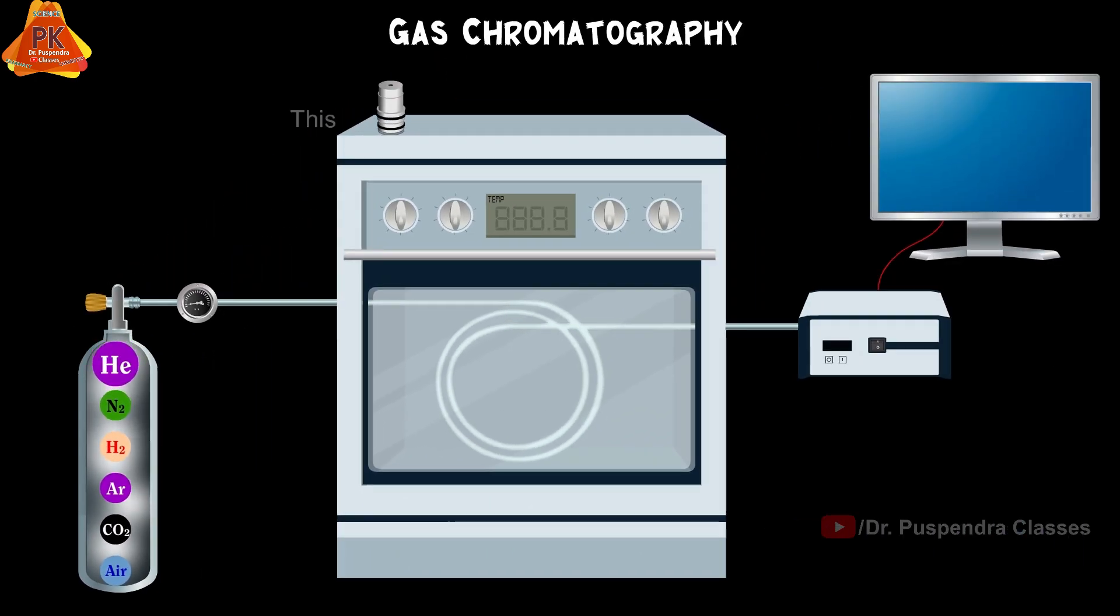The next part of the GC instrument is the gas controller. It helps to control the gas flow rate in GC. Pressure of gas should be in the range of 40 to 80 pounds per square inch.